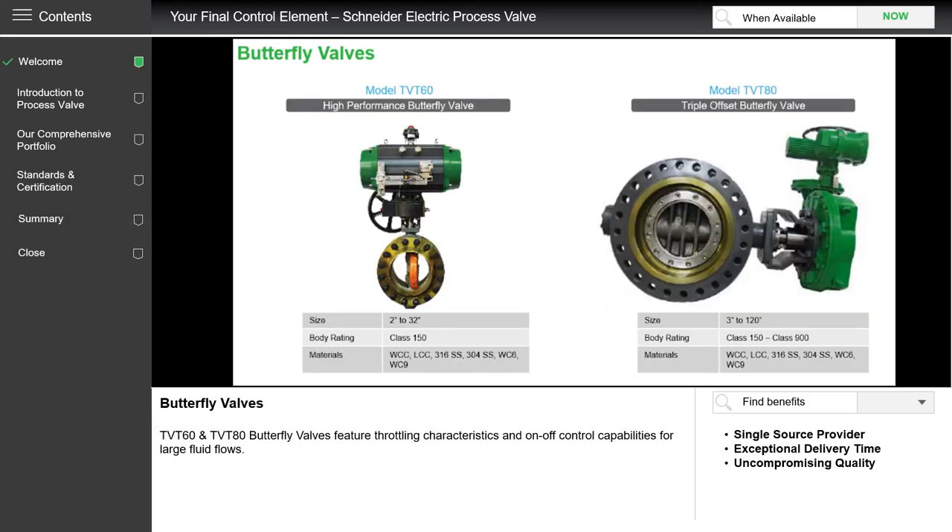Next up are the butterfly valves. The one on the left is the TVT60. It is a control valve that goes up to 32 inches or 800 millimeters. It is very good for liquids and gases, has a very good level of control, comprehensive build materials and is able to serve in different types of applications. The one on the right, the TVT80, is a triple offset butterfly valve. It can go up to ANSI Class 900 and the size can go up to 120 inches, which is almost three meters in diameter.